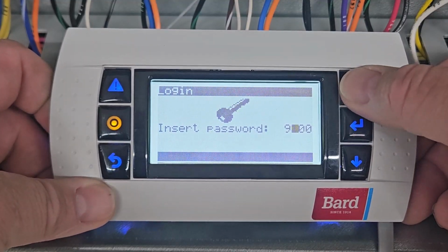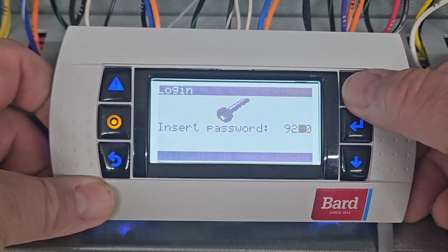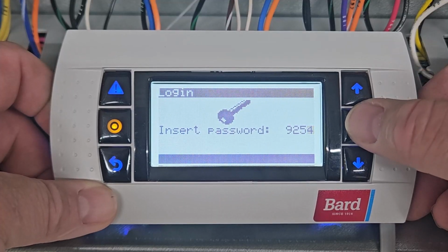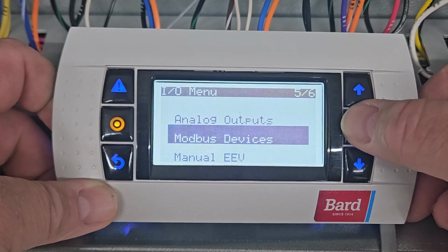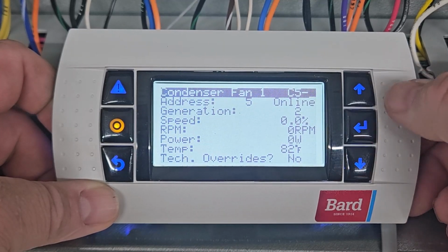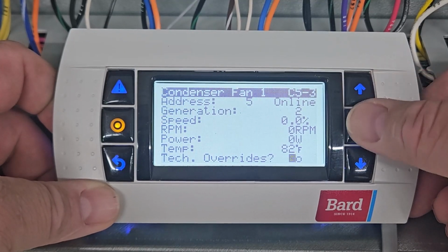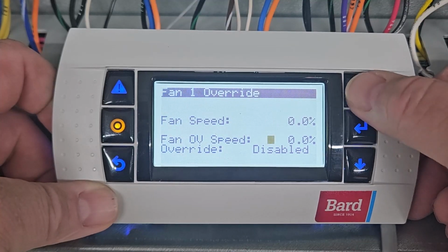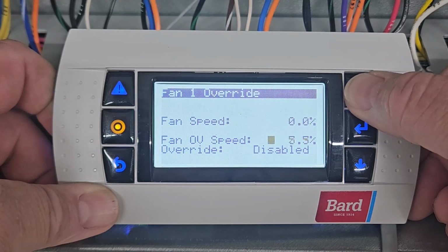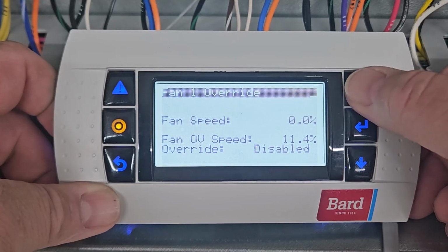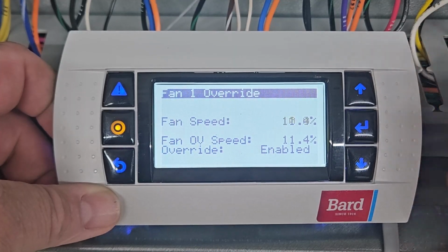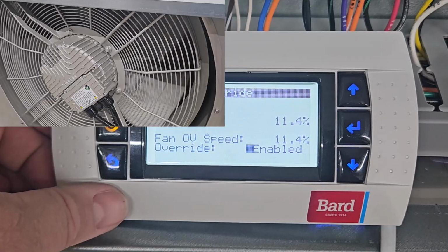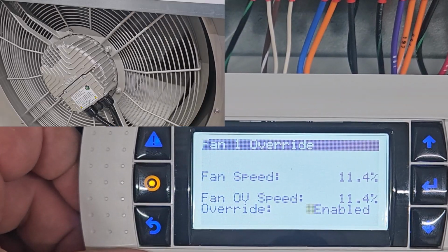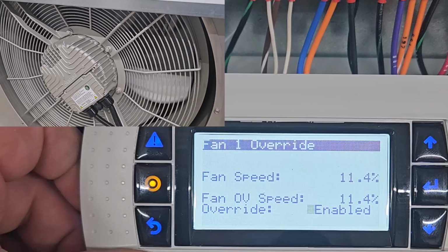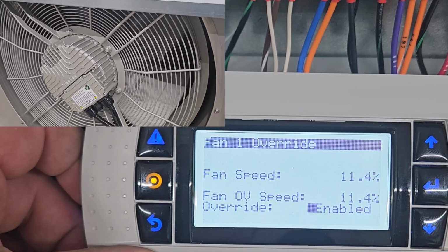Enter the engineering password and navigate to the I/O configuration menu. Navigate to the Modbus devices, find the condenser fan motor, and navigate down to the Tech Override. Input value yes. This will take us to a screen that will allow us to command the motor on by percentages and engage the condenser fan motor. The condenser fan motor can be increased and decreased as desired from this menu option.